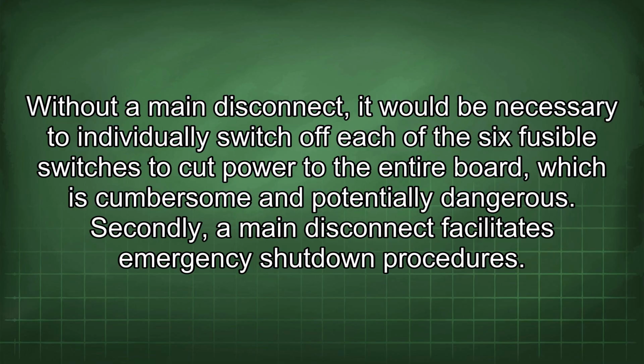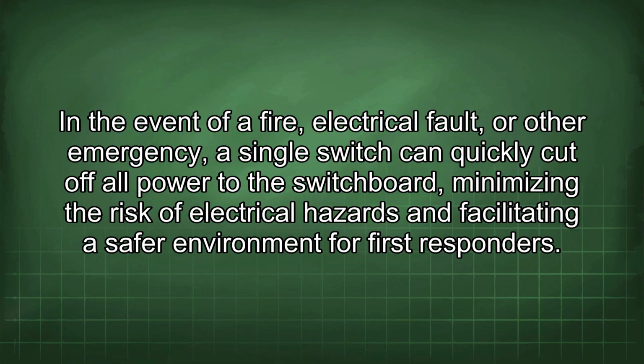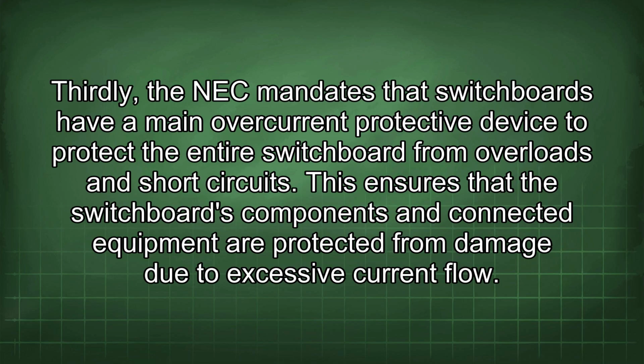Secondly, a main disconnect facilitates emergency shutdown procedures. In the event of a fire, electrical fault, or other emergency, a single switch can quickly cut off all power to the switchboard, minimizing the risk of electrical hazards and facilitating a safer environment for first responders. Thirdly, the NEC mandates that switchboards have a main overcurrent protective device to protect the entire switchboard from overloads and short circuits. This ensures that the switchboard's components and connected equipment are protected from damage due to excessive current flow.